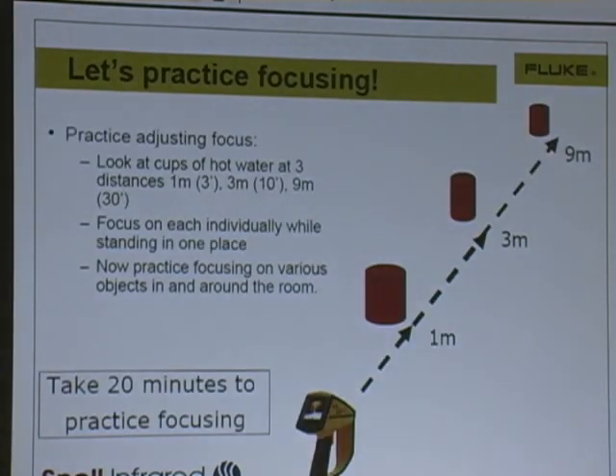Okay. Here's what I was trying to tell you earlier: the distances at which a camera will see. If you take a 1-inch object and start backing away, we did this in one class where they had what they call a black body. It's like a projector with a black lens on it, and it has a perfect emissivity of one. You're supposed to back away until you can't see it anymore. That tells you the absolute range of your camera, and they're all around 21 feet.